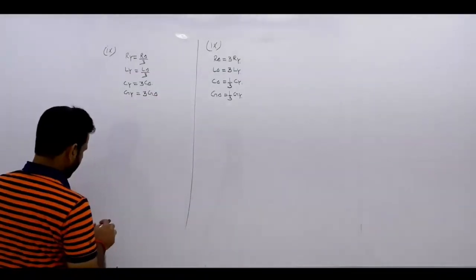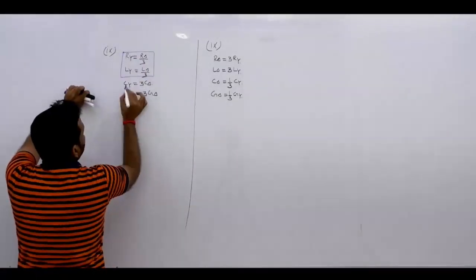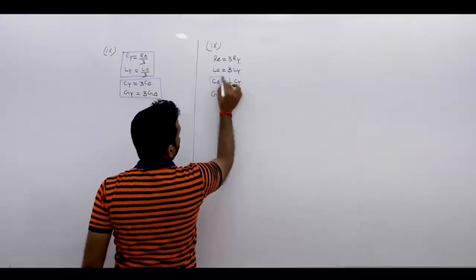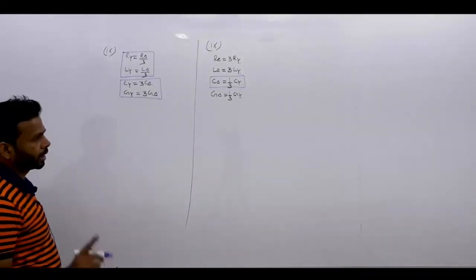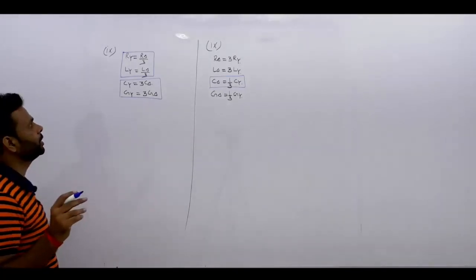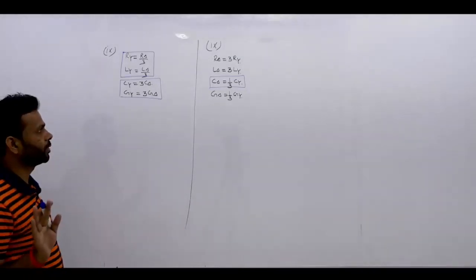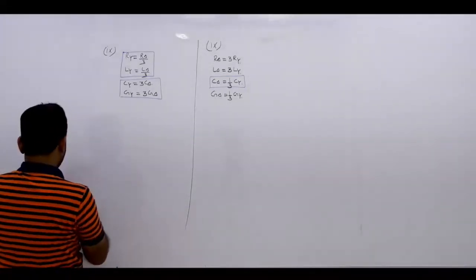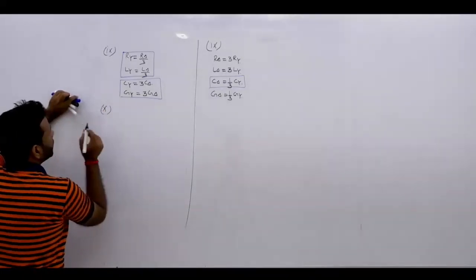So what we should note here is that these are the same thing and these are the two different things. This is the reason that when you take a capacitor bank in delta connection, the size of the capacitor bank is reduced by 1/3 as compared to the star connection. That's why in three-phase power factor improvement, the capacitor banks are connected in delta. Now the 10th point.